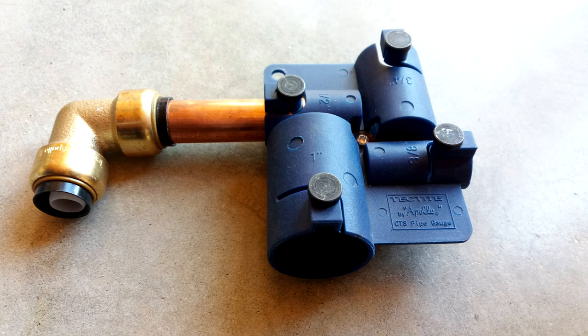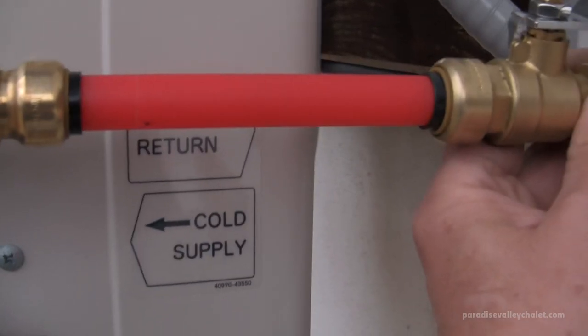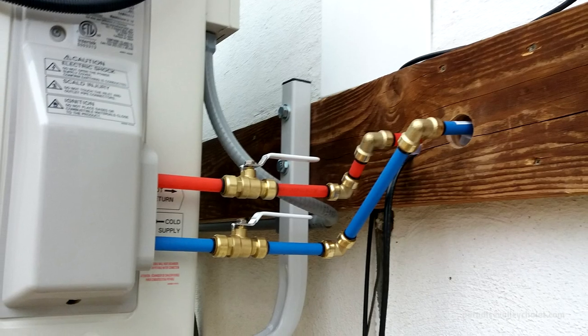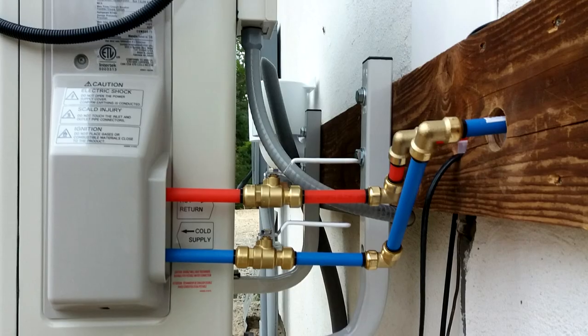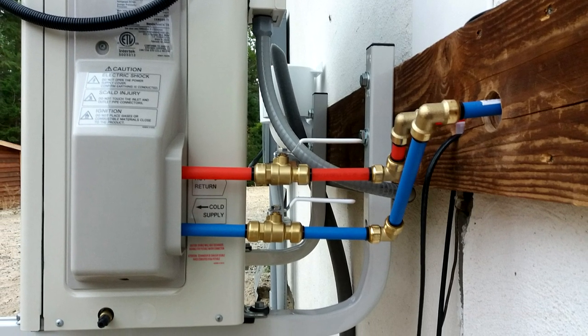You can get a Tectite or SharkBite deburring and depth gauge tool — it'll round off the edges of your cuts and mark the insertion length. The insertion length is about an inch, give or take depending on pipe size, so you'll want to calculate that in when you cut your plumbing. We've got our cold supply and our hot return looking nice, and we just popped through into the building.